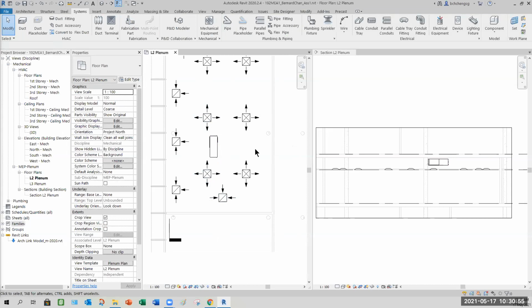So always remember, if you're doing design work and your company says you have a few mechanical equipment options that can be applied on this model, choose the one with the easy connection. When I say easy connection, what do I mean? As an aircon supplier, when there's too many turns, meaning there's a lot of disturbance or turbulence because of the blockage, see now, that causes turbulence. Turbulence will have sound, that's one thing. It will also slow down the flow, which is not so good. Eventually the ducting at further ends might not get enough air. We'll get wind, but maybe not cold, due to the turbulence. So a design with less bending and fewer turns is better.